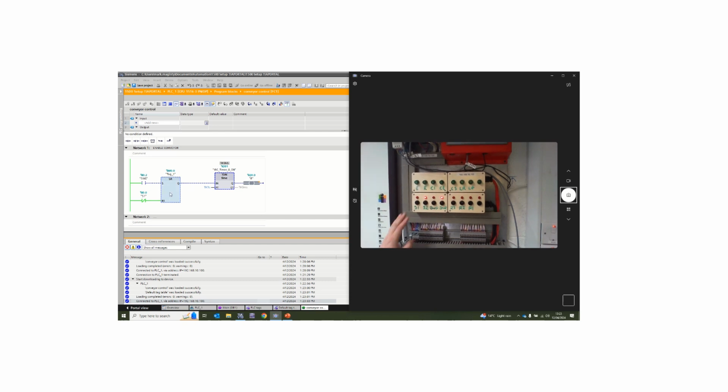So if you now lift the part away, that would effectively go back to being on, and it means you can now press the button over again for SWG, and you can let go, 3 second delay, the output turns on, it traverses down, and then eventually arrives at S1 and turns itself off. So that's a method of getting, in this case, the conveyor to turn on after a delay, travel down the conveyor, and then turn off via one of the sensors.